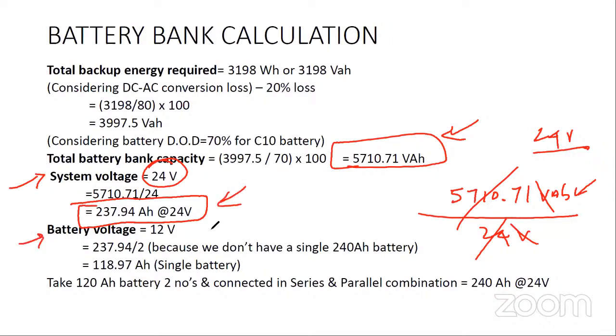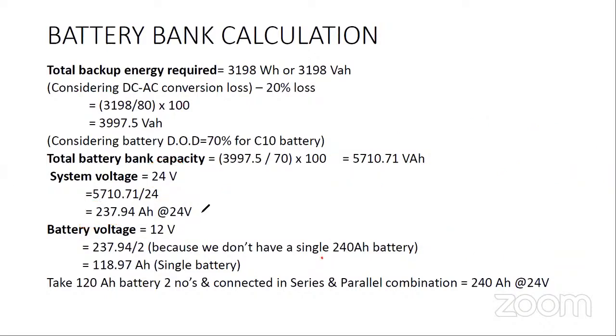But a single battery is 12 volt. So if I can connect 237 Ah of battery in series, my problem is solved. But unfortunately, we don't have a single 240 Ah battery. The maximum battery available is 220 Ah. So I am in a necessity to split this circuit into two networks. What I'm doing is rounding off this 237 to 240 Ah. This 240 is divided into 120 and 120 each. So now it becomes two circuits.